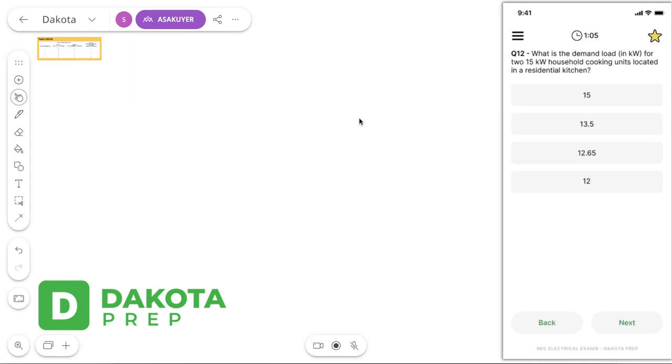And welcome to Dakota Prep's video for how to find our demand for household cooking equipment. So we're gonna use this question over here to tackle this subject. It says, what is the demand load in kW for two 15 kW household cooking units located in a residential kitchen? Okay, so since we're looking for demand for our load, we know we're in Article 220.